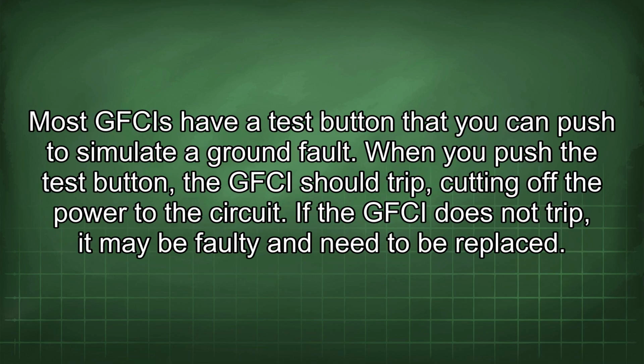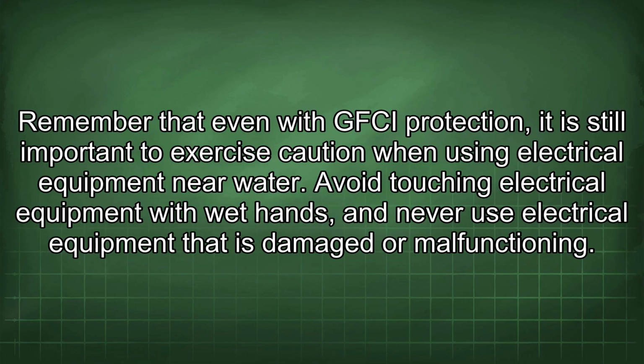Most GFCIs have a test button that you can push to simulate a ground fault. When you push the test button, the GFCI should trip, cutting off the power to the circuit. If the GFCI does not trip, it may be faulty and need to be replaced. Remember that even with GFCI protection, it is still important to exercise caution when using electrical equipment near water. Avoid touching electrical equipment with wet hands, and never use electrical equipment that is damaged or malfunctioning.